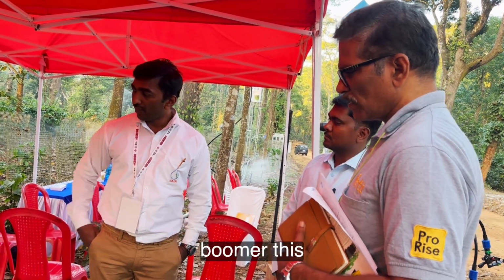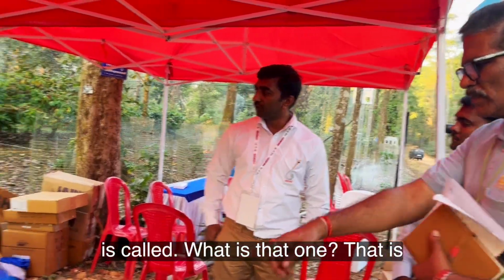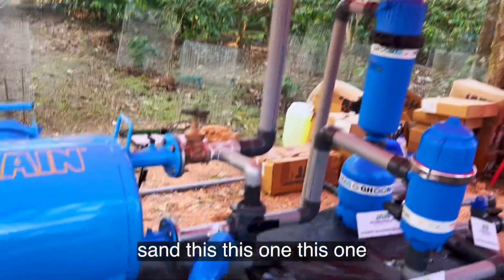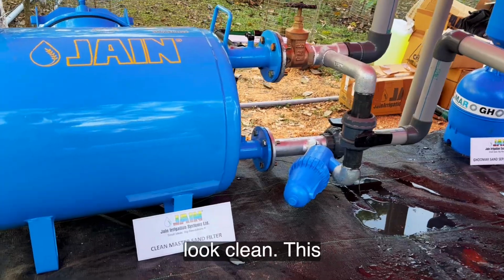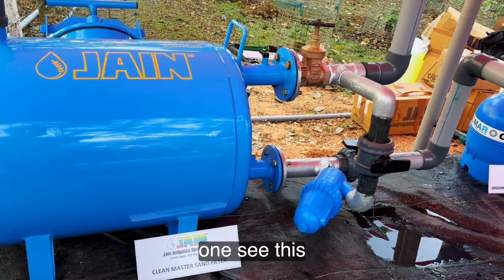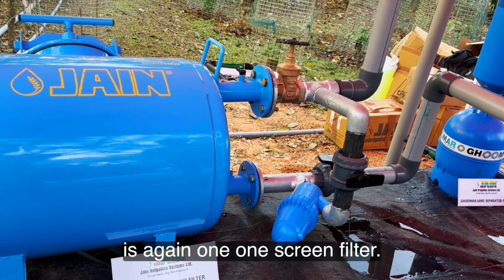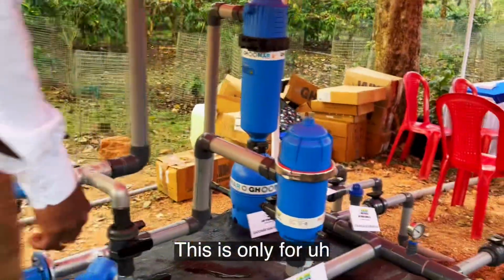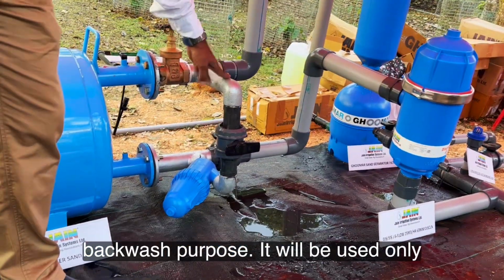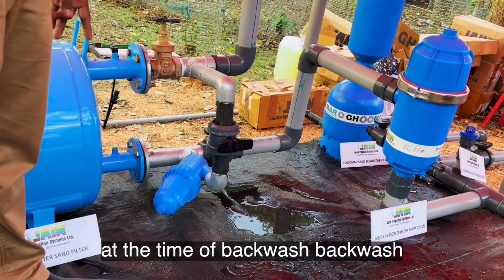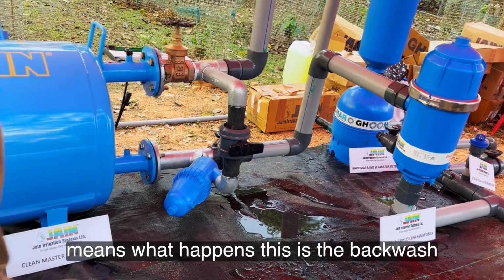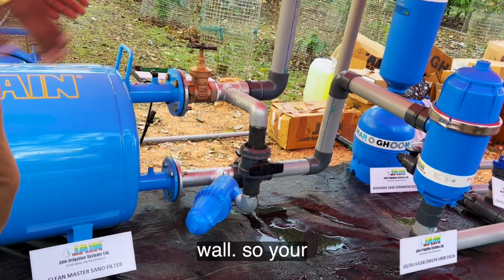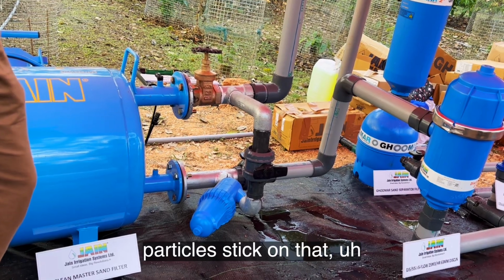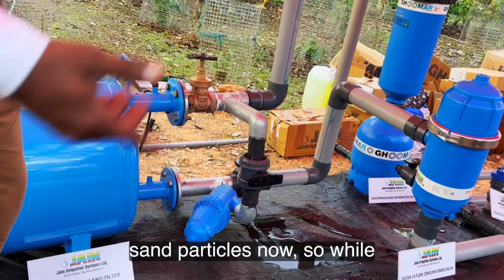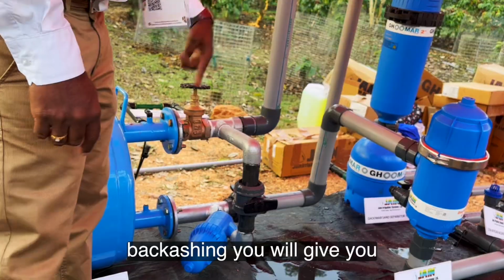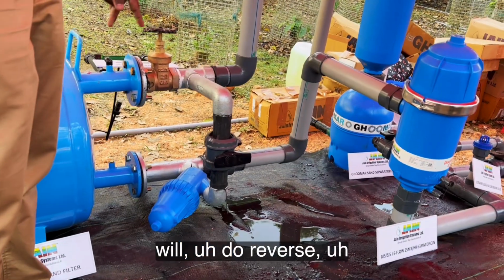This is a sand filter. This blue one is the Clean Master. This is again a screen filter, used only for backwash purposes. Backwash means, this is the backwash valve. Your particles stick on the sand particles, so while backwashing you do a reverse operation.